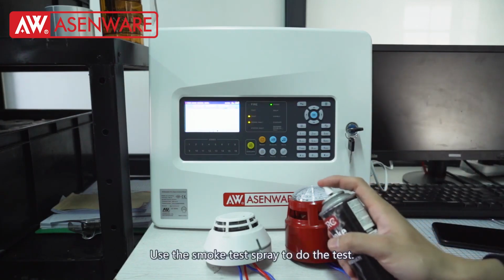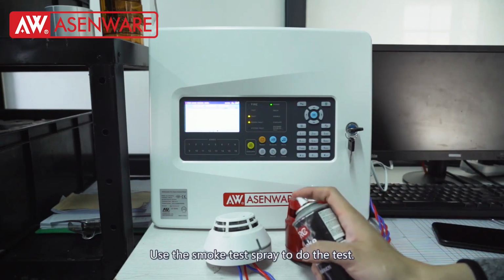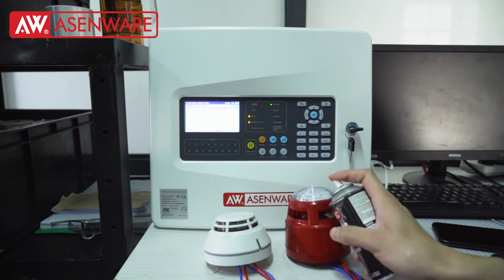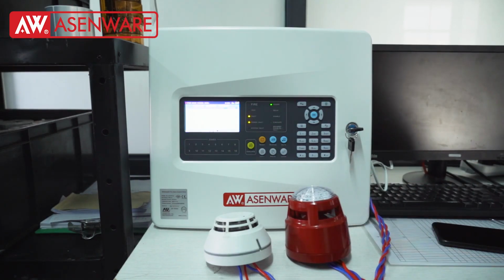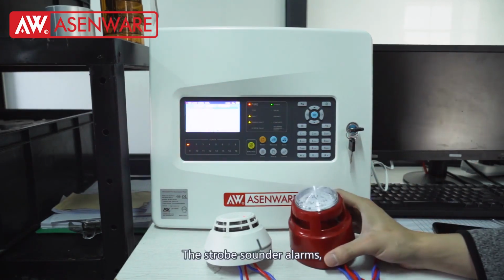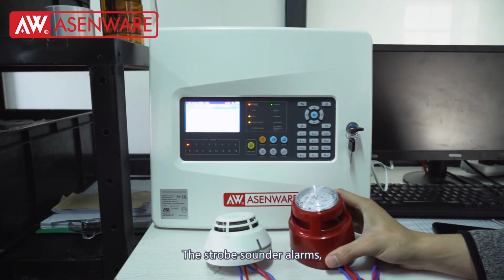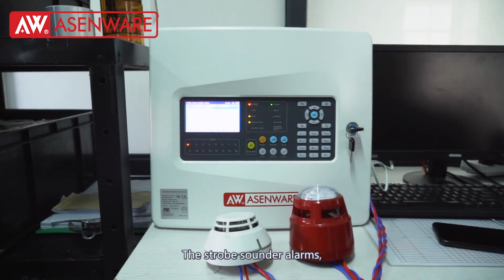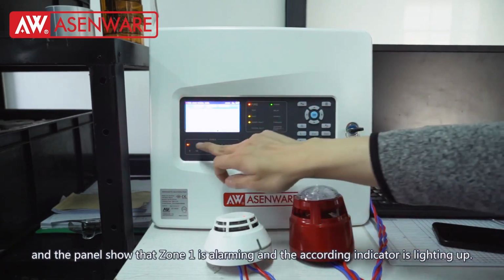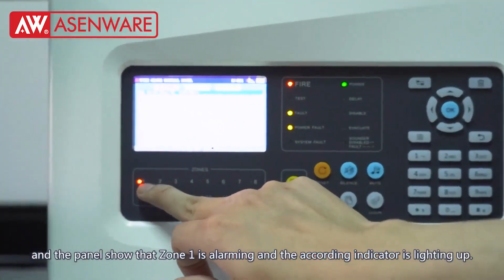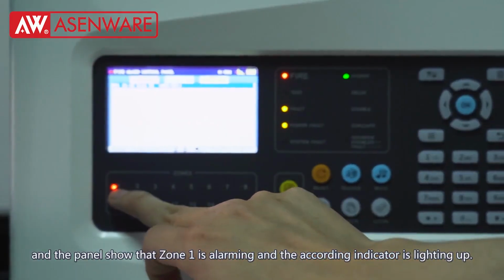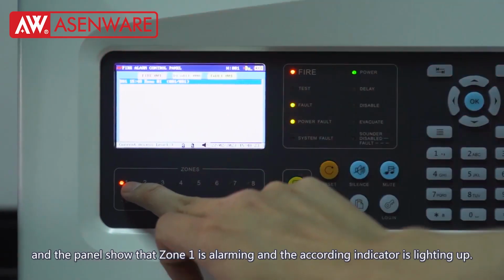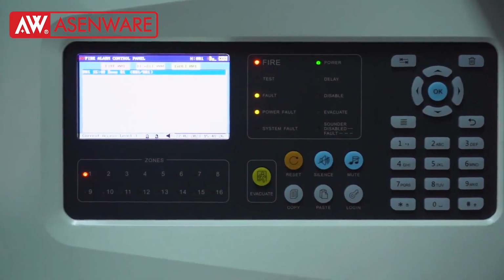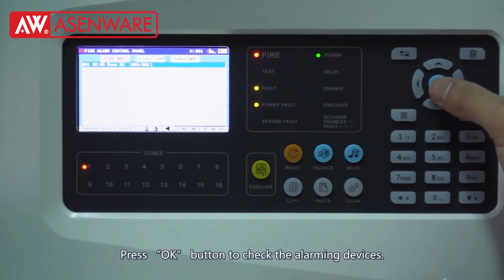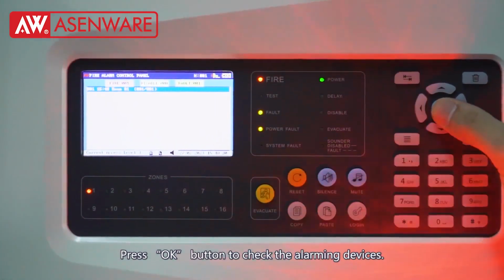Use the smoke test spray to do the test. The strobe sounder alarms. And the panel shows that Zone 1 is alarming and the according indicator is lighting up. Press the OK button to check the alarming devices.